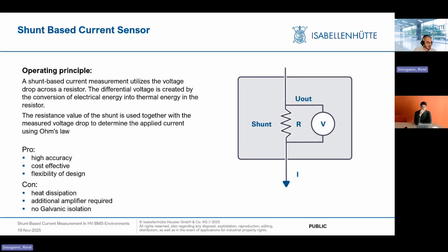You do have power loss here because it's standing directly in the way of the current, but you have the most accurate voltage drop that you can read off compared to other solutions that you might get. So you can imagine just having a voltmeter at both ends of the shunt, at the shunt terminals, and get the high accuracy and flexibility of design. But then again, you have to deal with heat dissipation, like the 15 degrees Celsius that we just mentioned. You also need other components that increase the total cost of ownership, and there's no galvanic isolation, which has to be handled by the other components mentioned.